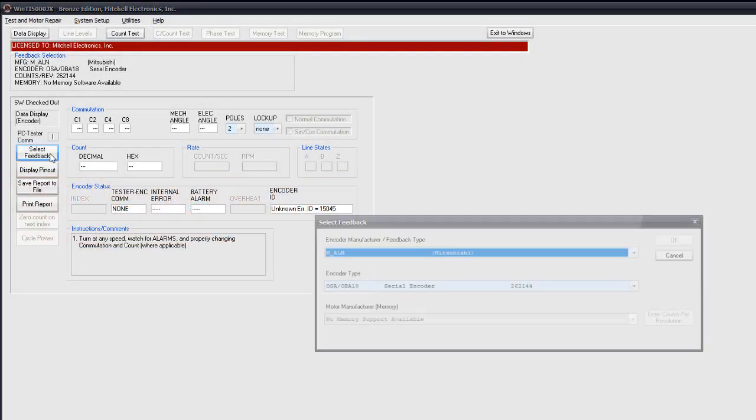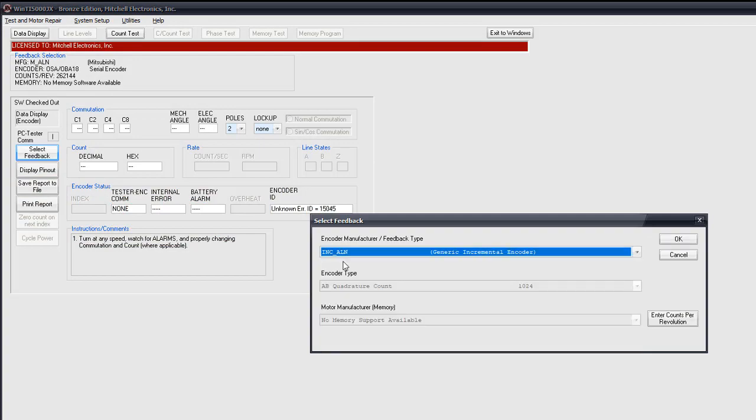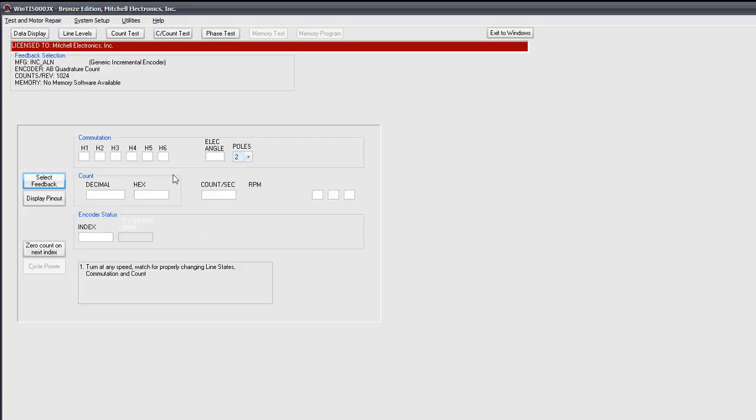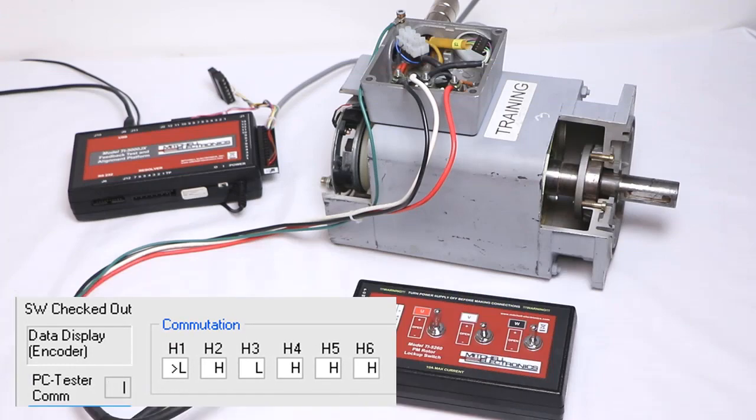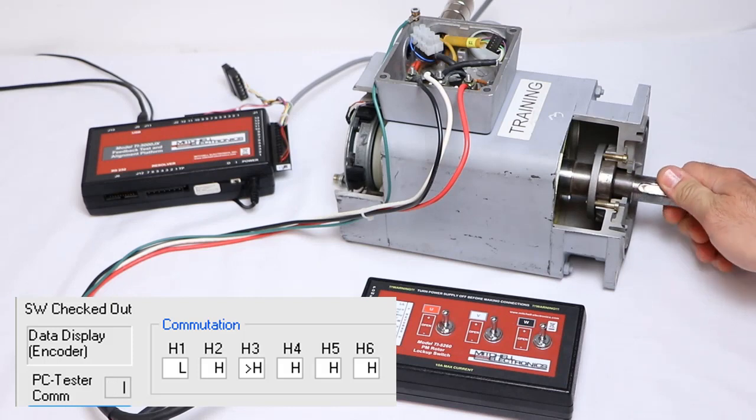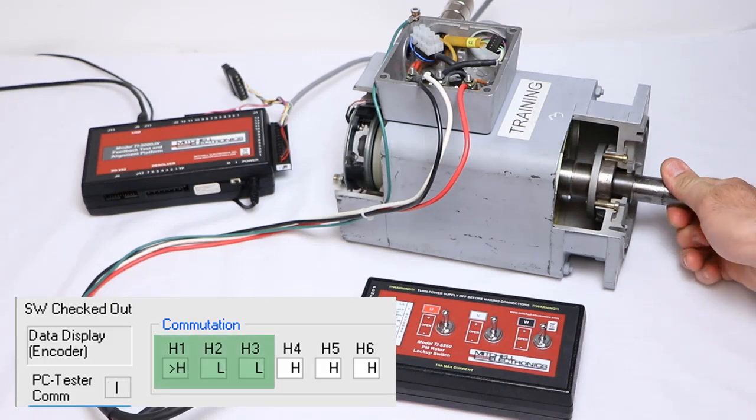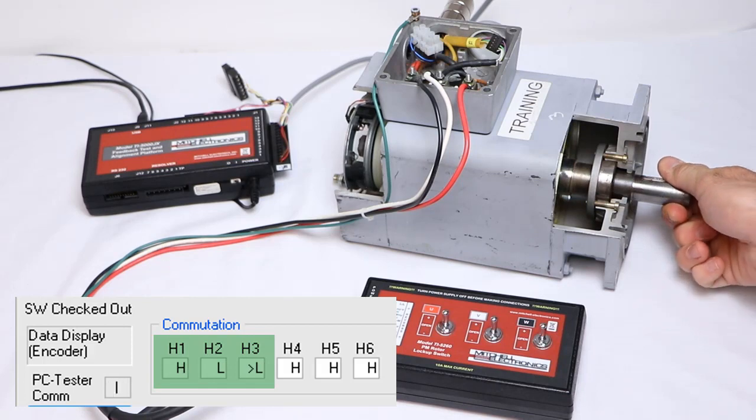These commutation states can be seen in the data display of generic incremental encoder selection. There are a minimum of three signals listed as H1, 2, and 3. To test they are working, simply turn the motor by hand and make sure that the first three signals are changing between high and low.